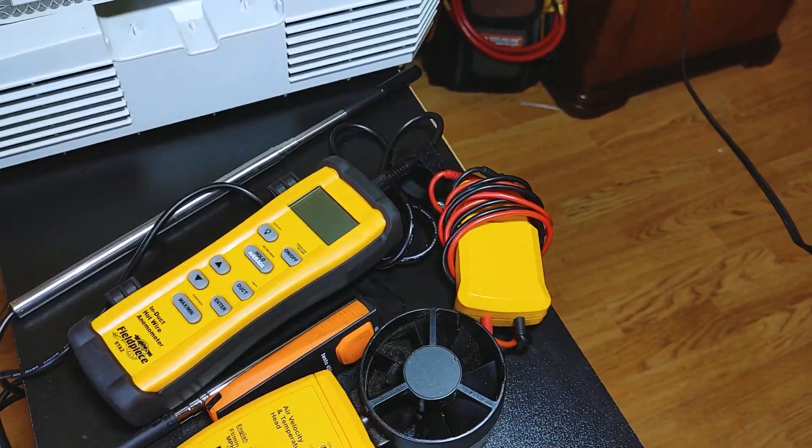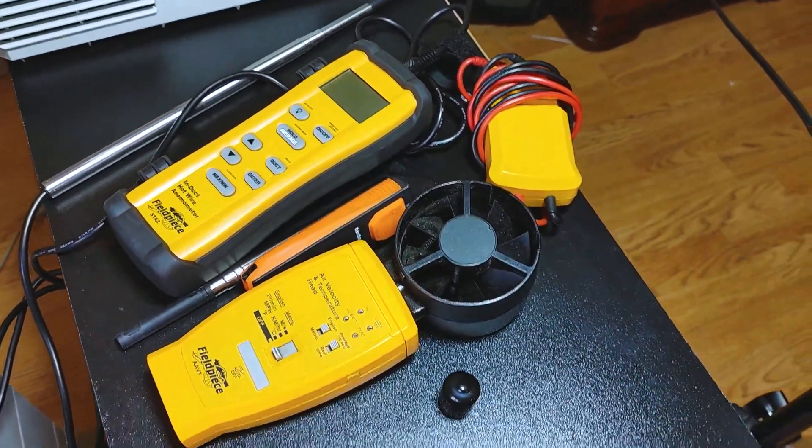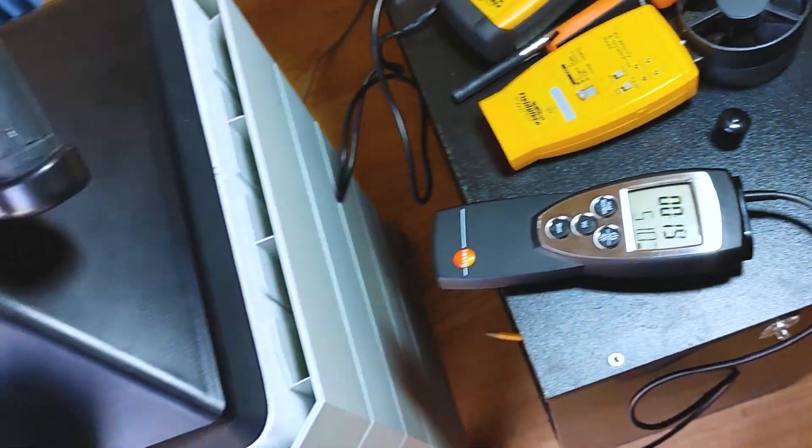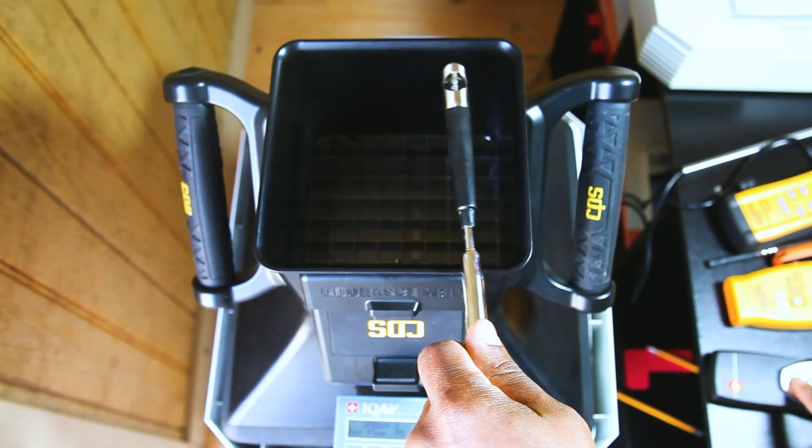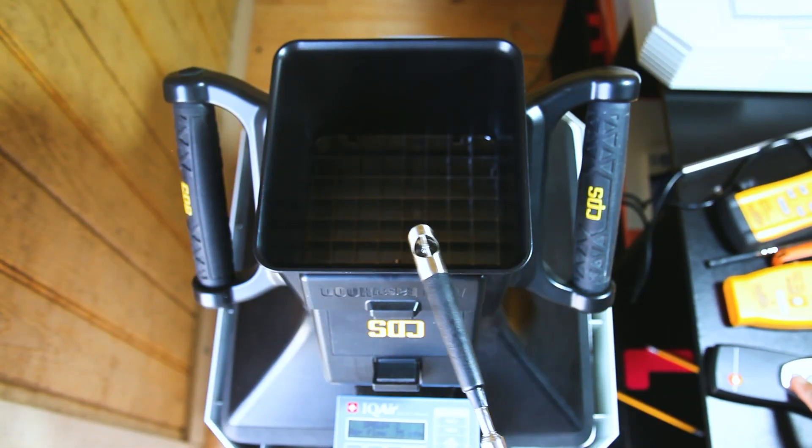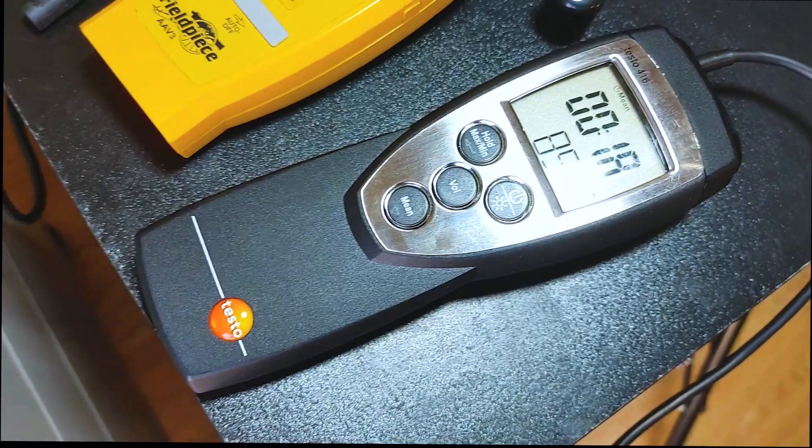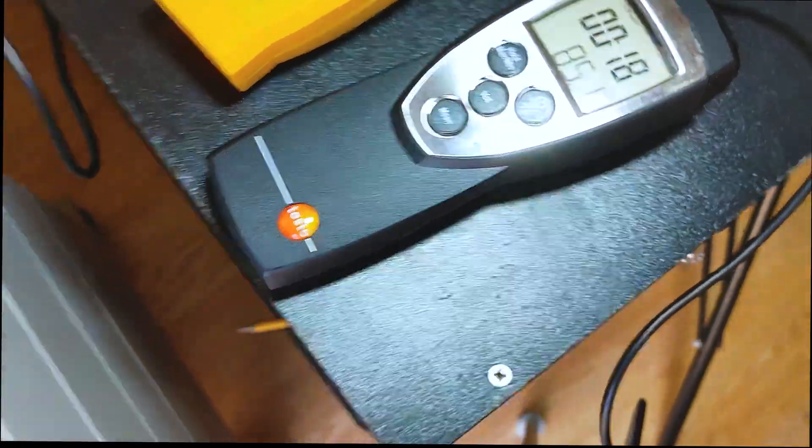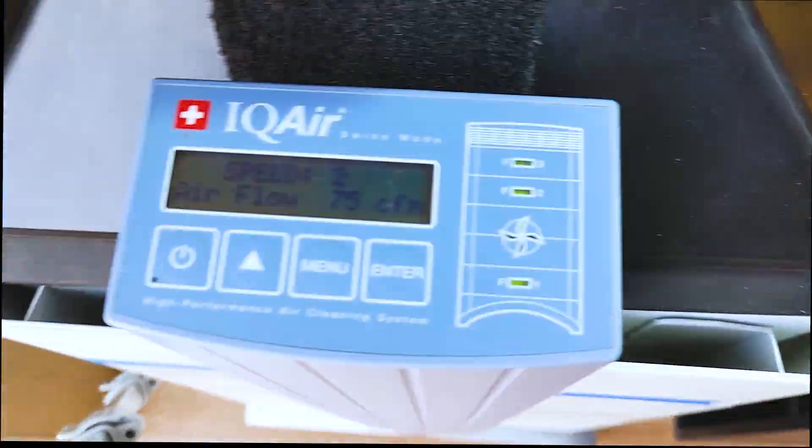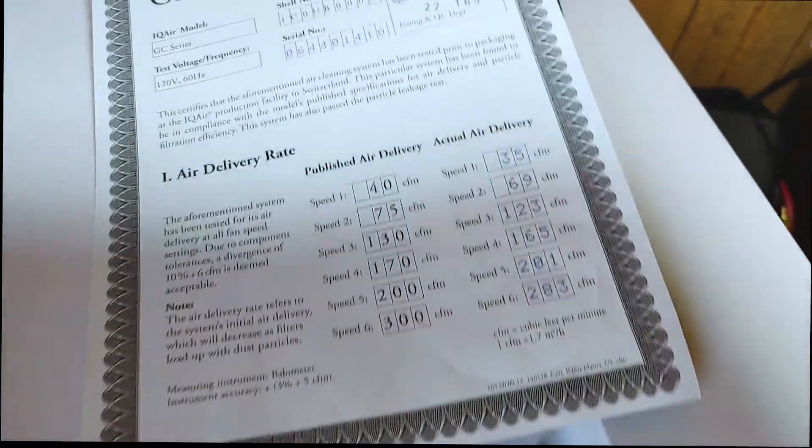So we're 10 CFM higher than the rated and 15 CFM higher than what the manufacturer put out. 85 CFM on speed two, should be 75, manufacturer got 69.